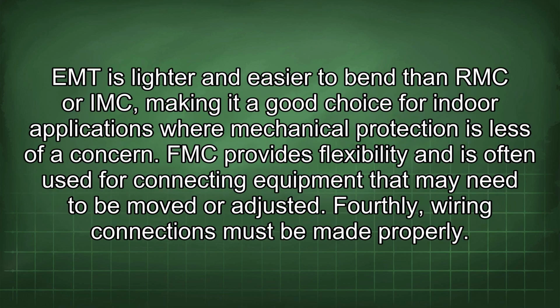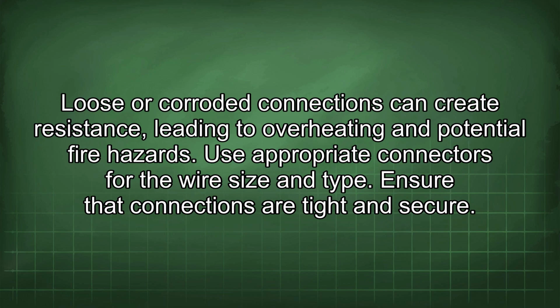EMT is lighter and easier to bend than RMC or IMC, making it a good choice for indoor applications where mechanical protection is less of a concern. FMC provides flexibility and is often used for connecting equipment that may need to be moved or adjusted. Fourthly, wiring connections must be made properly. Loose or corroded connections can create resistance, leading to overheating and potential fire hazards.